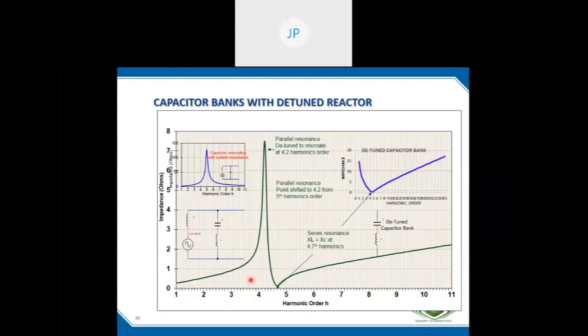Here, from this tuning point, the left side is reactive, inductive, and this point is capacitive. That is why this resonating point happens. So actually, this is intended to protect the bank. As this is low impedance near the fifth harmonic, there is a reduction of the fifth harmonic also.